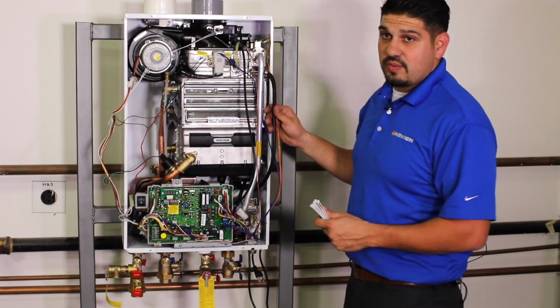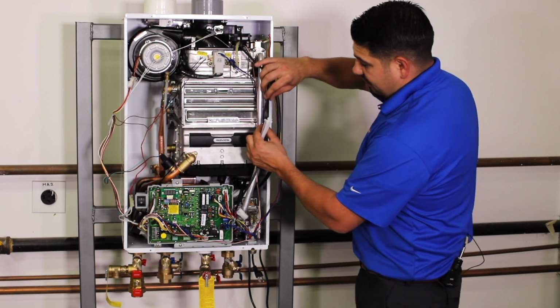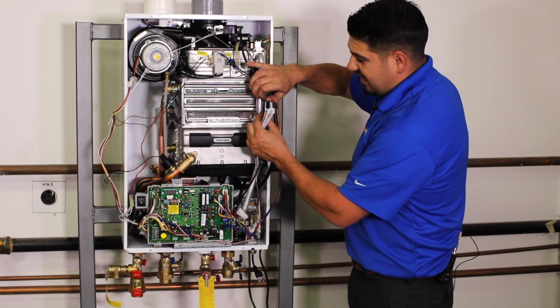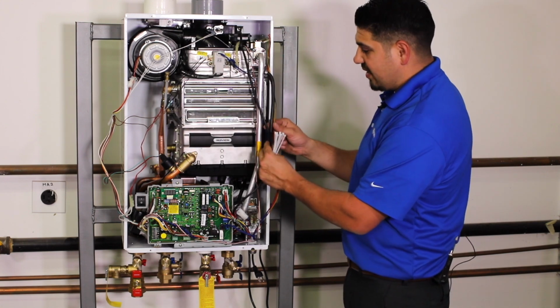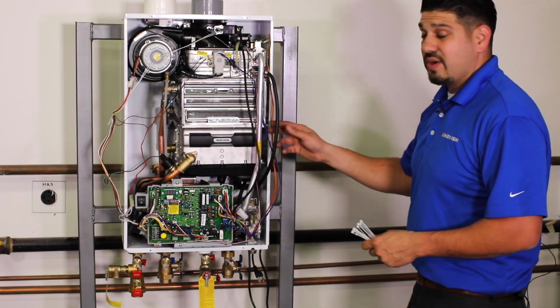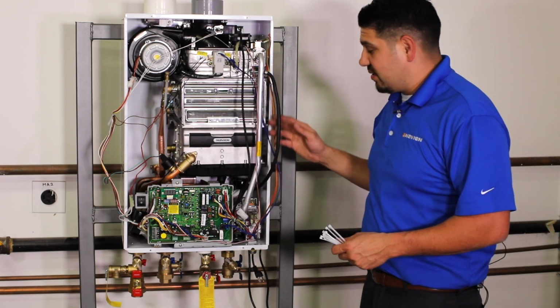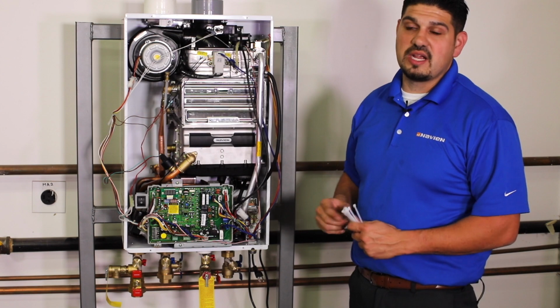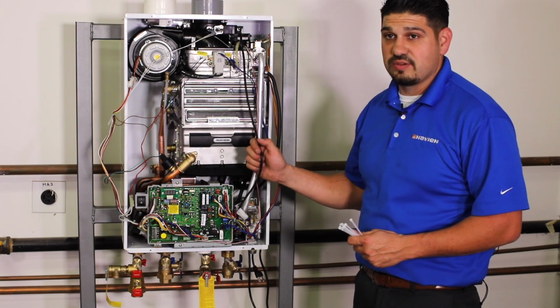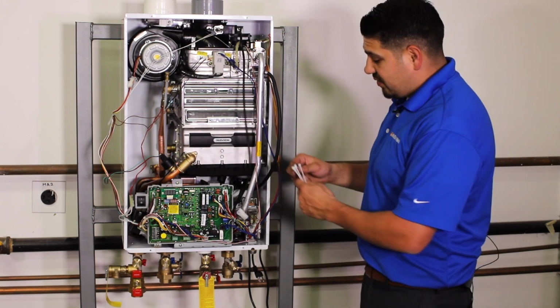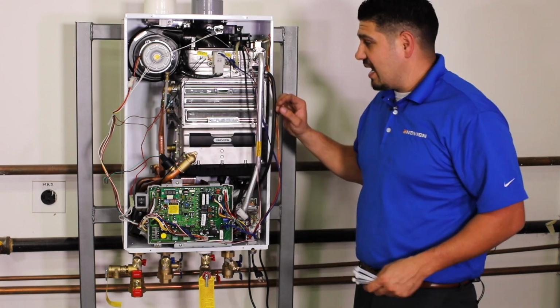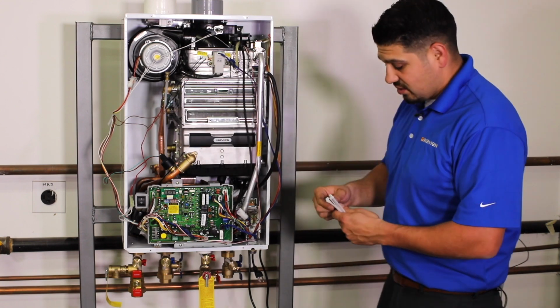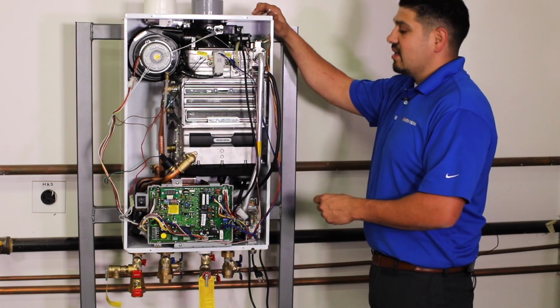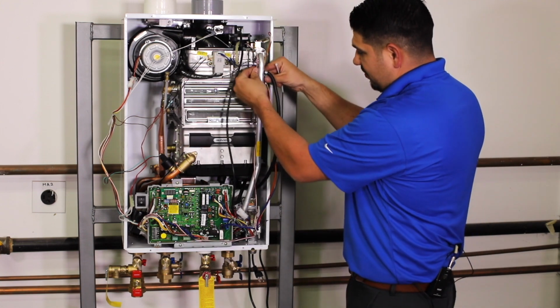Now, something you want to ensure when you're zip tying these is if you pull the zip ties too tight, what it's going to do is pinch these lines. And these lines are really critical to the operation of the unit. This is how the unit knows how much fuel and how much air is going through there, by measuring the pressure inside of this. So if you zip tie it and you wrench down on it, what's going to happen is you're going to pinch these two hoses. So take that into mind as you're putting your zip ties in, and make sure you don't pinch those.